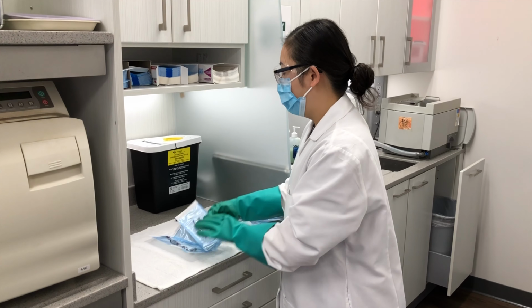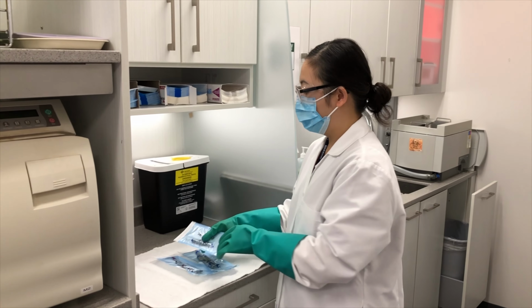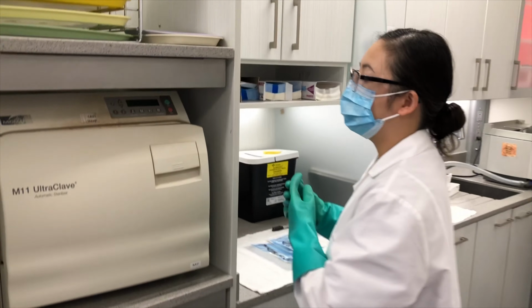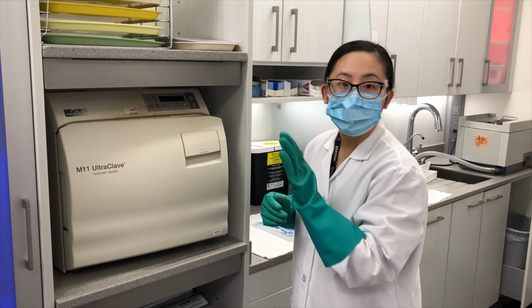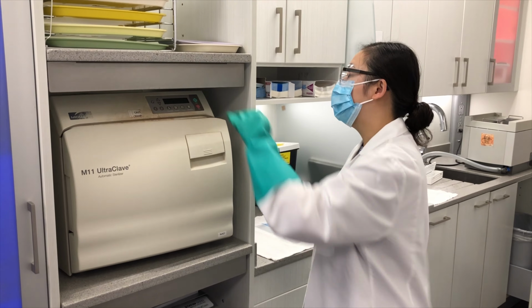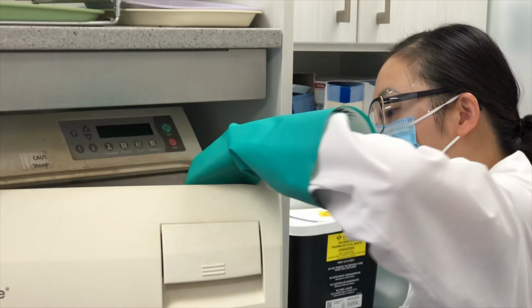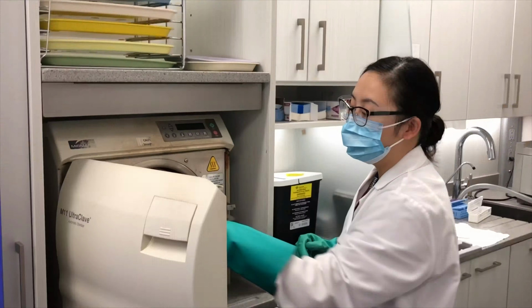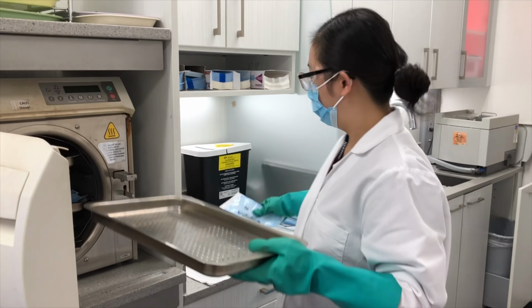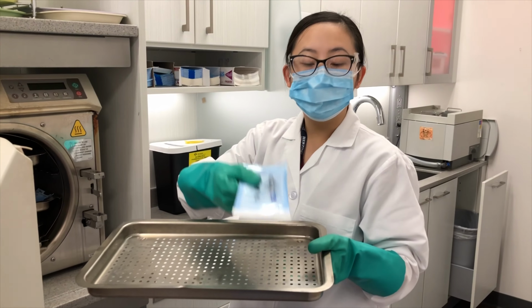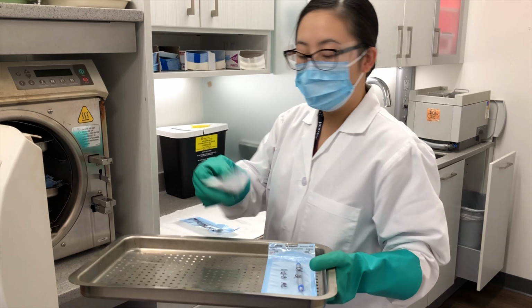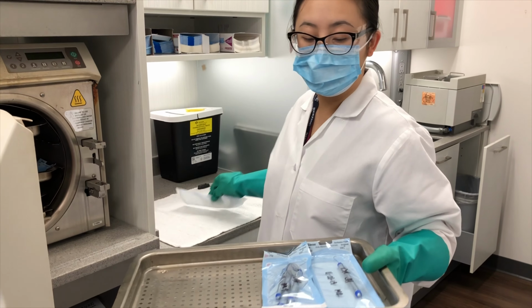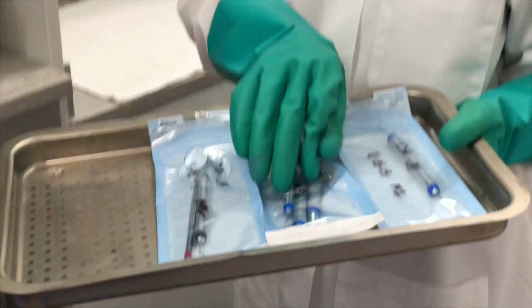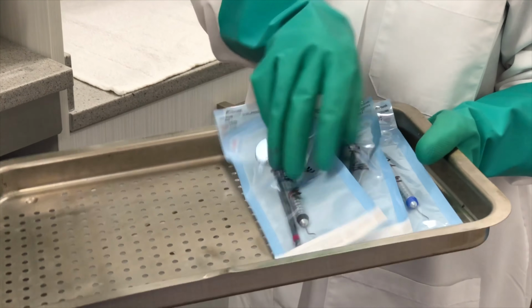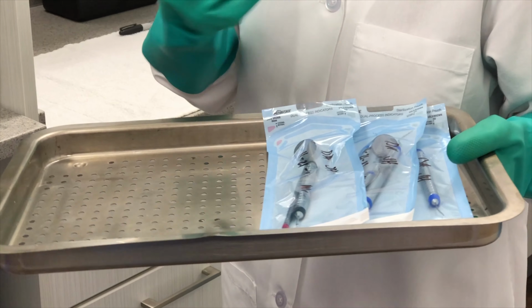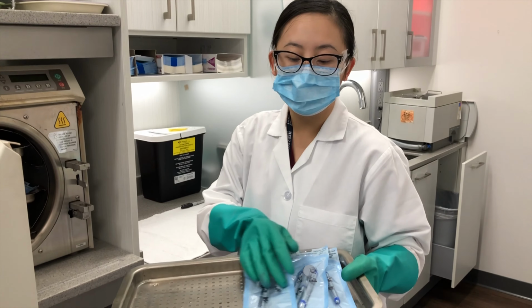Before you start loading the instruments into the autoclave, there must be enough packaged instruments to start a cycle. Do not touch the handle to the autoclave, as they're considered clean. Take out an empty tray and place the instrument pouches on the tray with the plastic side up. The sides of the instrument pouches should be touching each other. Do not overlap the pouches, since there should be a free flow of steam within and around the instrument packages.